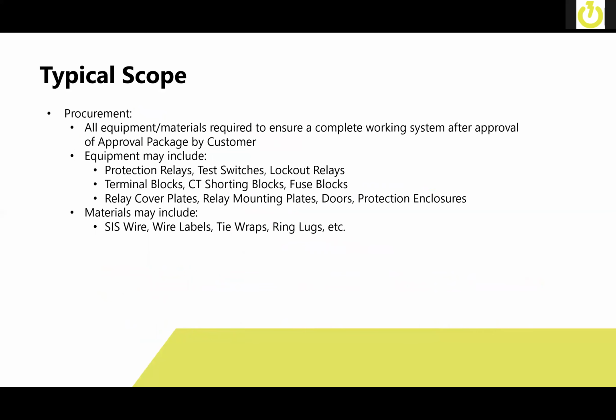From a procurement standpoint, we procure all equipment and materials required to ensure a complete working system after the approval of the approval package by the customer. A lot of times we get asked why we don't order equipment immediately up front, and a lot of times that has to do with making sure we are providing the correct equipment for your installation. For instance, a lot of relays come with options for 48 volt DC, 24 volt DC, 120 volt DC or AC control power supplies or input voltages. And we want to make sure that we match your system.